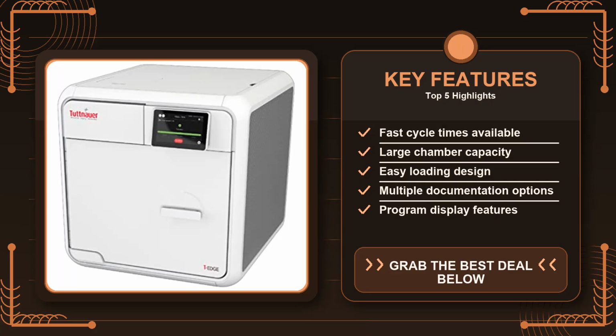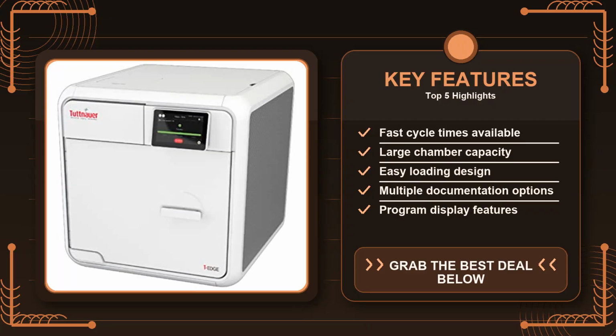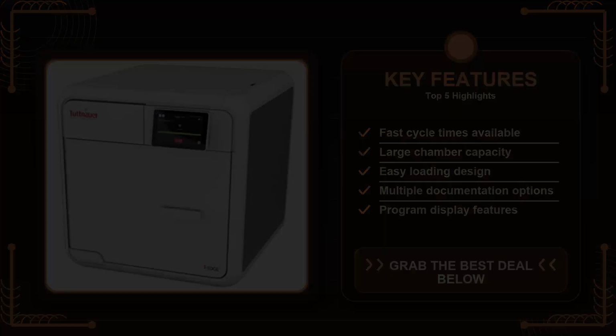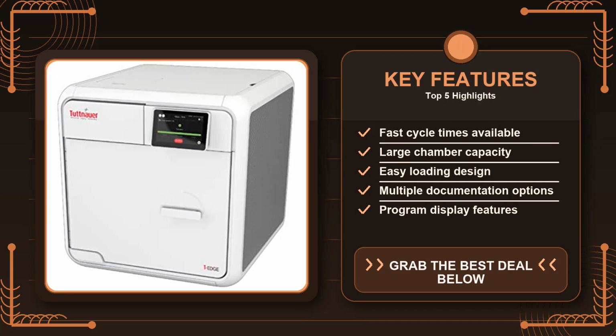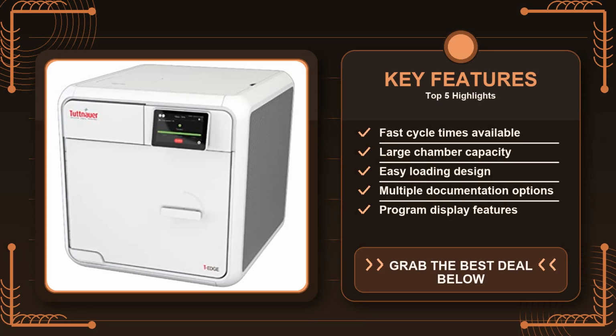In my test scenario, loading a full set of wrapped dental trays, the drying phase stretched an extra 10 minutes beyond the cycle timer. That's not a deal breaker, but it's worth knowing if you're counting on precise turnaround times. Another trade-off is the learning curve for the interface. The display is clear and colorful, but the menu system is layered, and it takes a few minutes to locate the exact program you need.